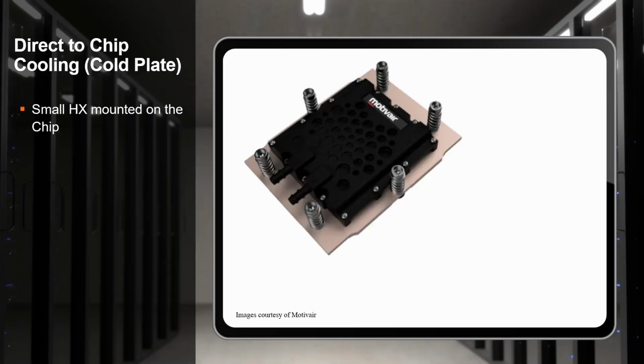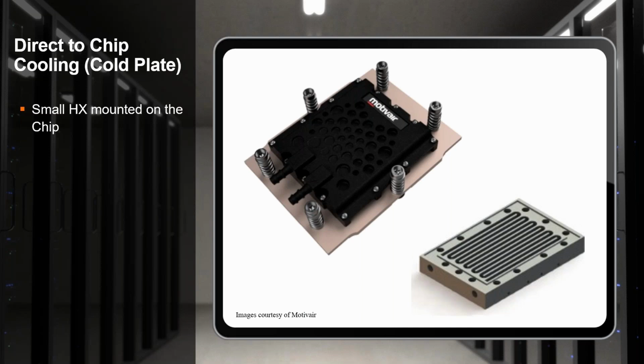So what is a cold plate? A cold plate is just what we talked about. It's a little heat exchanger. It's like a block of metal with some channels milled in it, and we're going to put our fluid through there. And they're not all that large. If you've never seen one in person, they're a little bit larger than maybe a deck of cards, and they're designed to sit directly on top of the processor chip. So it doesn't cover the whole server, and that's why we might have as many as 4 or so cold plates on a single server, because they're sitting directly on the processing chips that are on top of there, removing the heat.